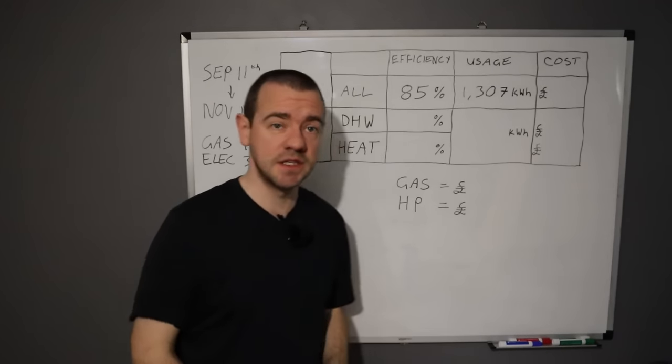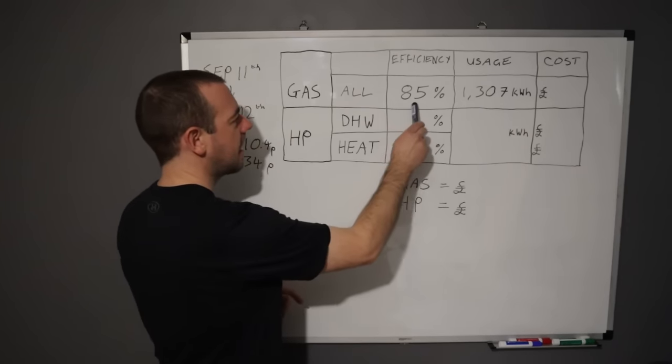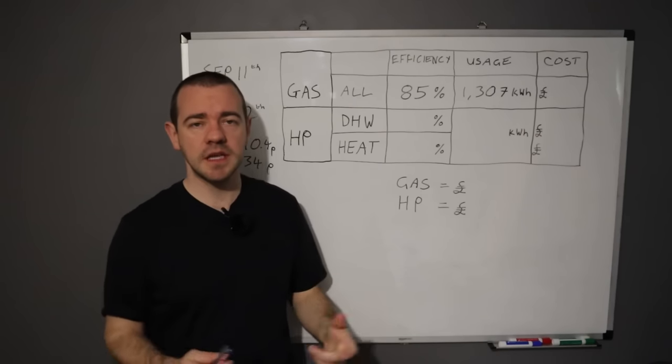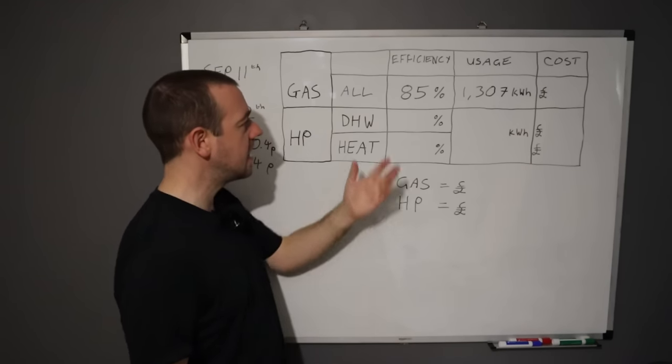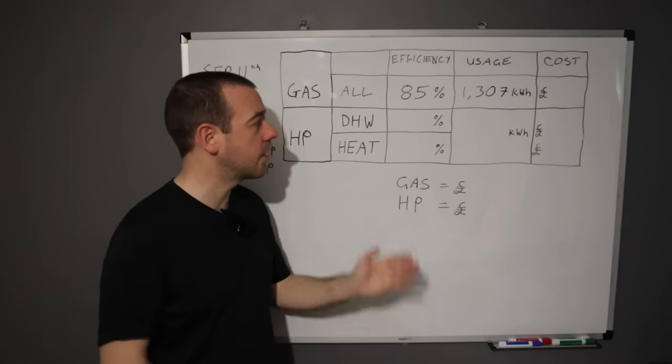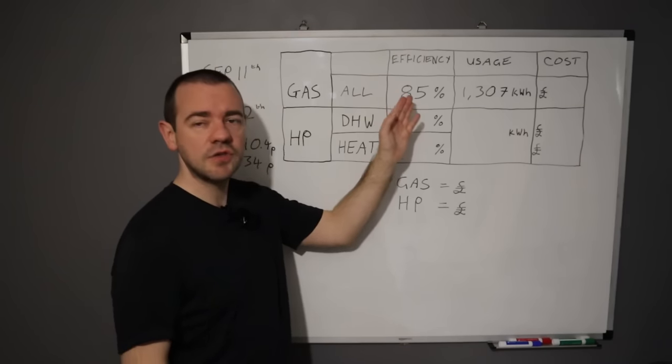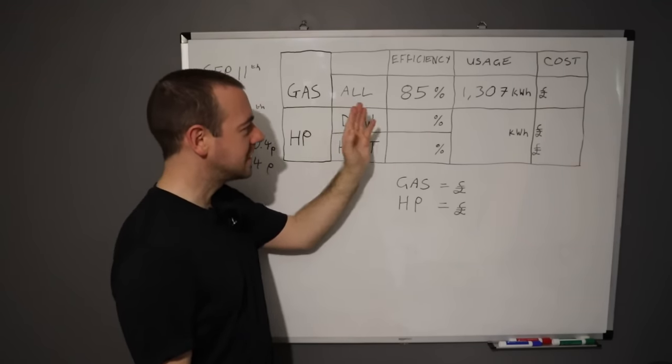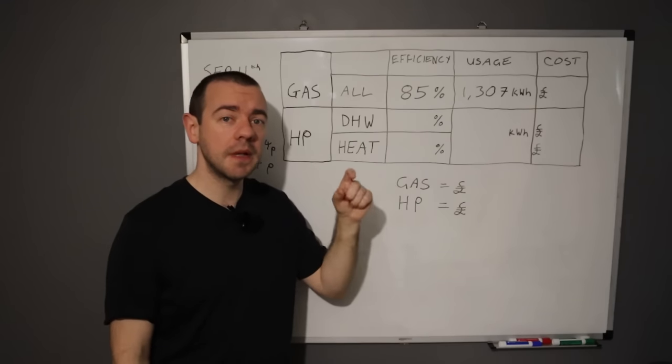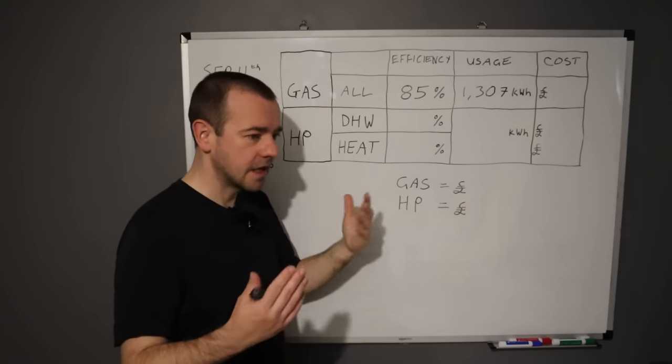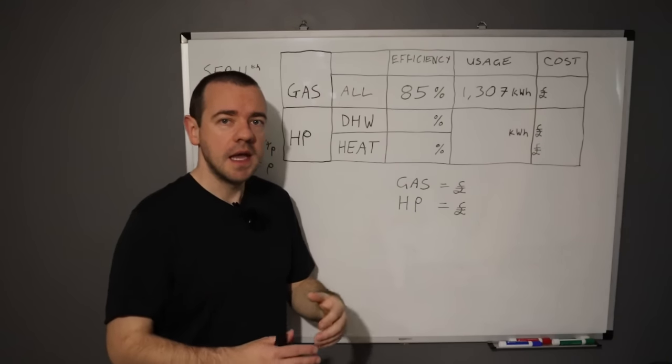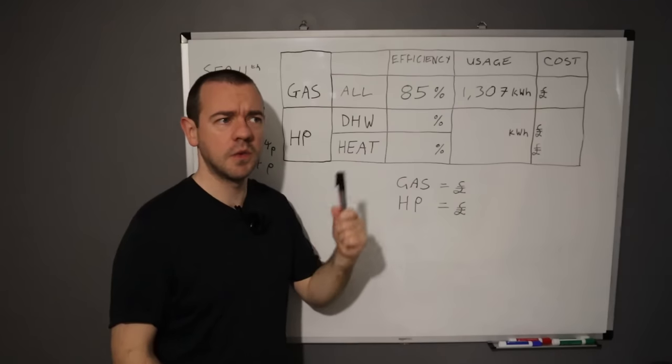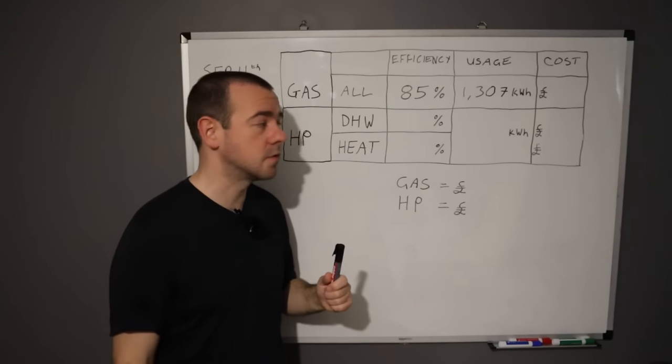Let's look at the efficiency now of the gas boiler. I picked 85% efficient because that's what everybody seems to be telling me in the heating industry and online. In reality mine's probably a bit lower than that because again like most out there it's well oversized, not the most efficient install which was done presumably when the house was built.